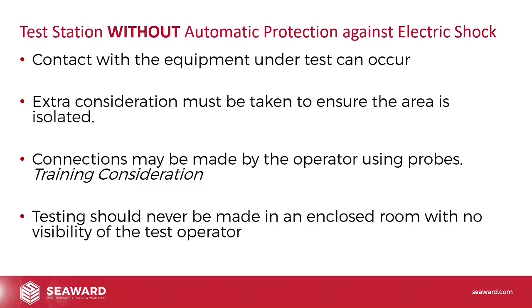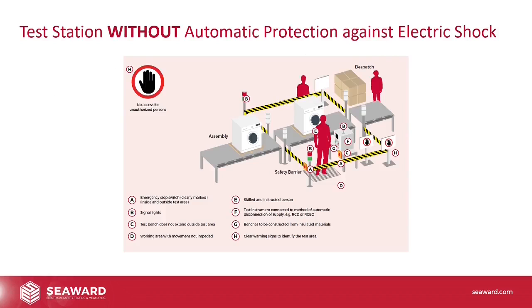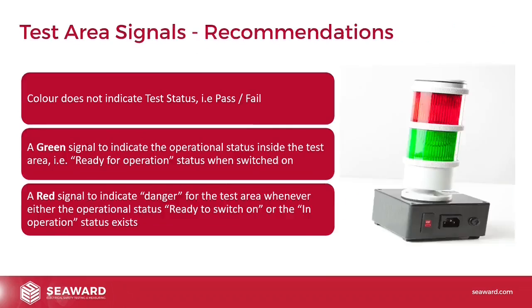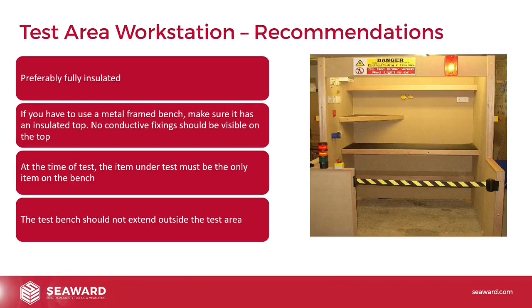But again, I can't emphasize this enough, testing should never be made in an enclosed room with no visibility of the test operator. So never in an enclosed room, guys. This is what a gold standard, if you like, test station without automatic protection looks like. This is a kind of production line. Now, if I just jump back a few slides here, it might be that this kind of setup is better for you. Again, we're just applying the same things to a lot of different situations.